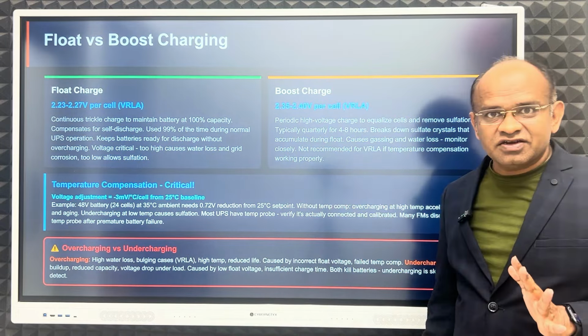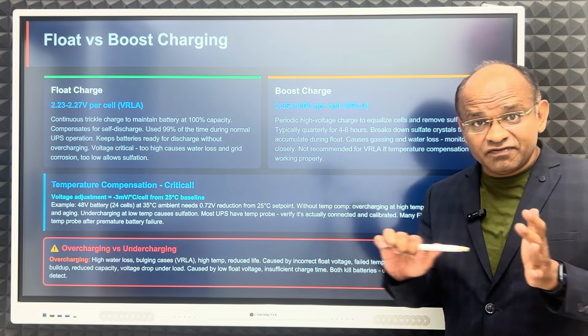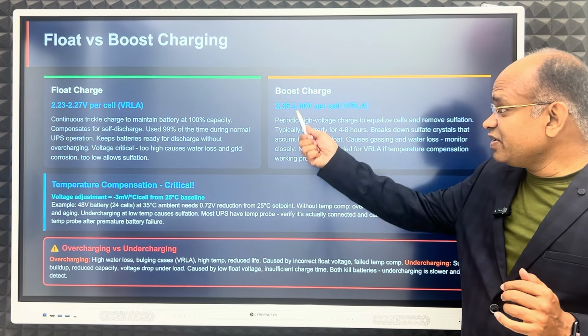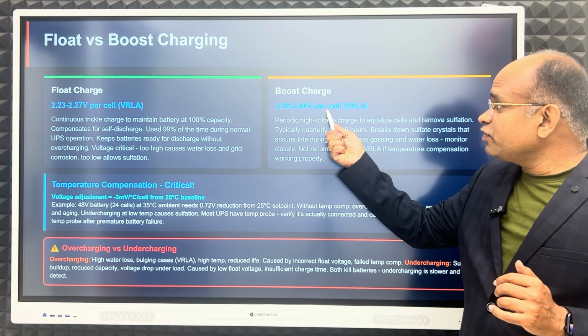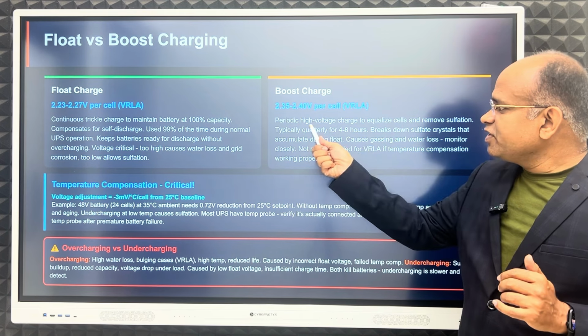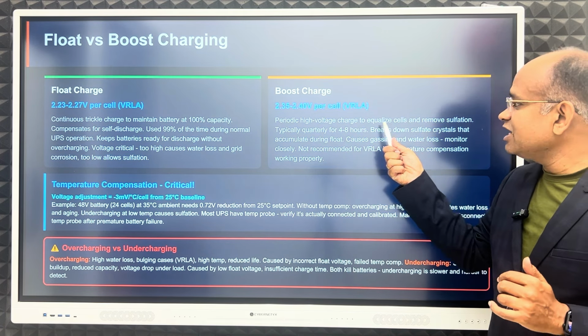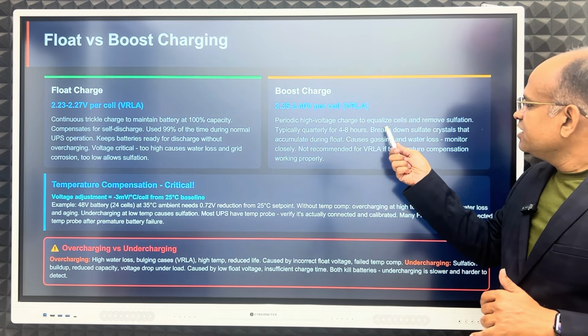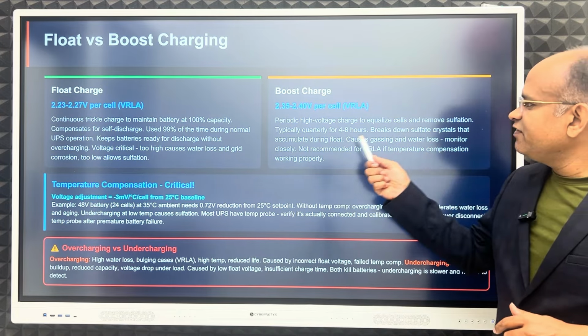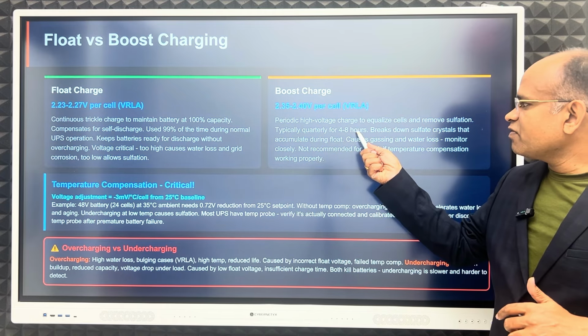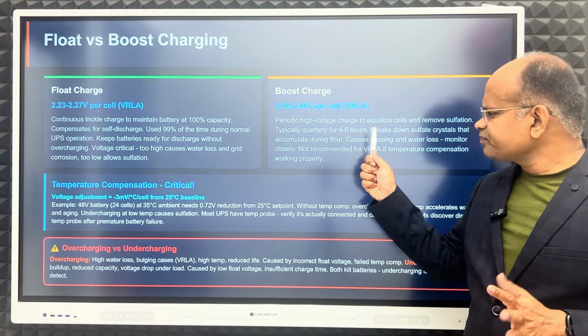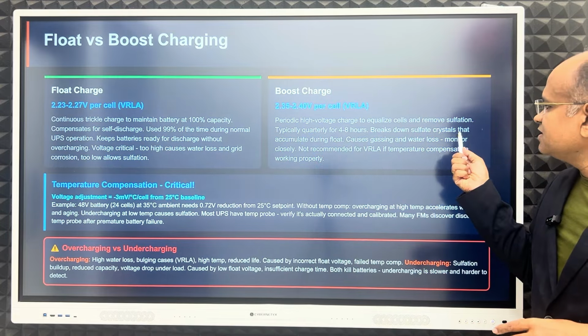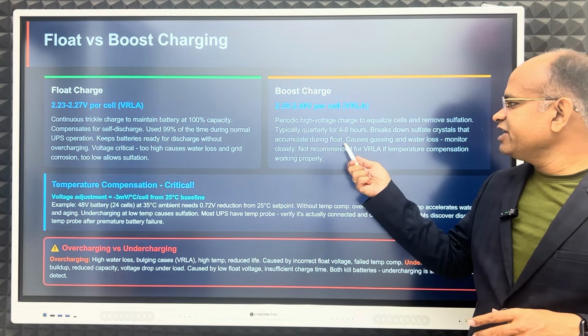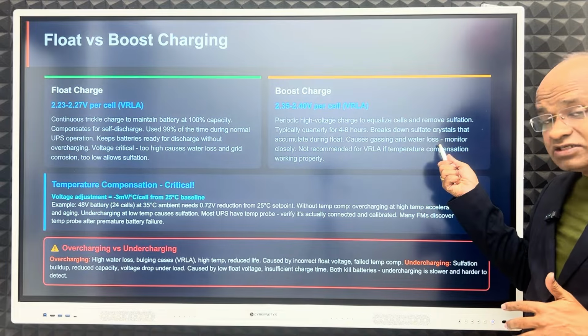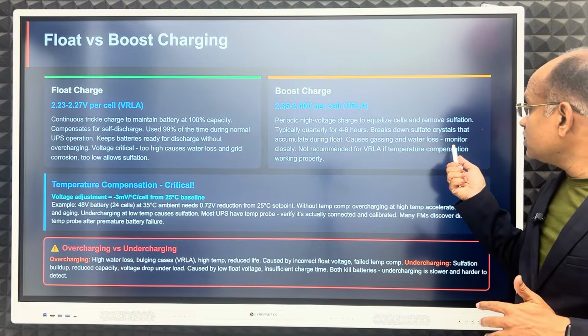Now boost charge, very fast. Boost charging is happening for our electric vehicles. It is 2.35 to 2.40 volt per cell. It is a periodic high voltage charge, periodic, not every time, to equalize cells and remove sulfation, typically quarterly for 4 to 8 hours. It breaks down sulfate crystals that accumulate during float. It will cause gassing and water loss.